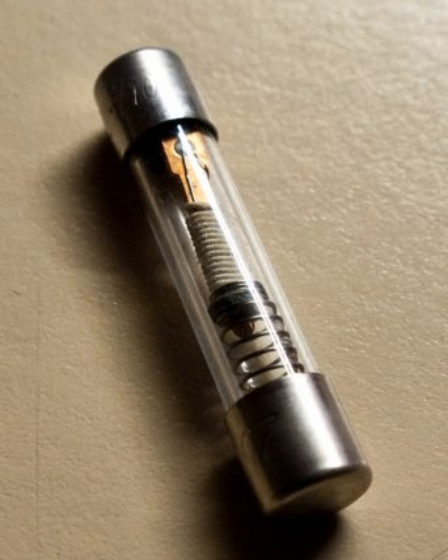Medium voltage fuses may have liquid-filled envelopes to assist in the extinguishing of the arc. Some types of distribution switchgear use fuse links immersed in the oil that fills the equipment. Fuse packages may include a rejection feature such as a pin, slot, or tab, which prevents interchange of otherwise similar appearing fuses. For example, fuse holders for North American Class RK fuses have a pin that prevents installation of similar appearing Class H fuses, which have a much lower breaking capacity and a solid blade terminal that lacks the slot of the RK type.